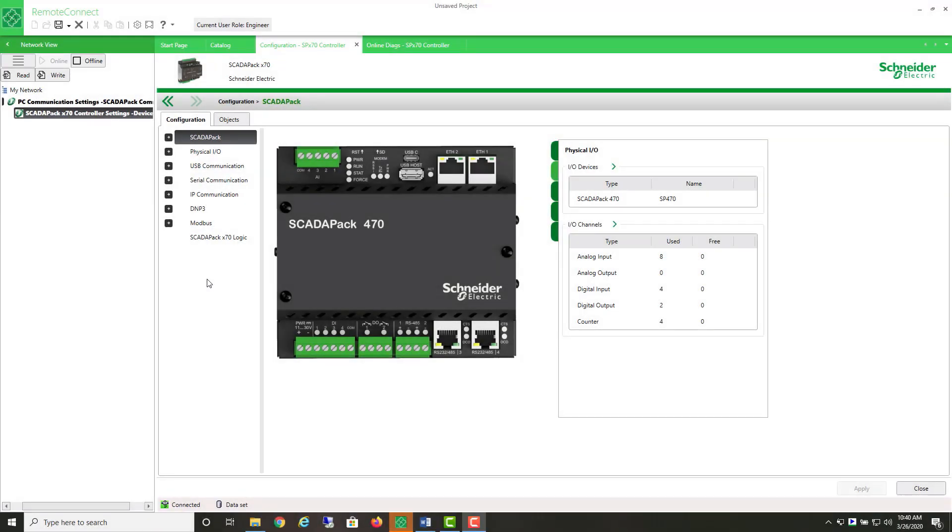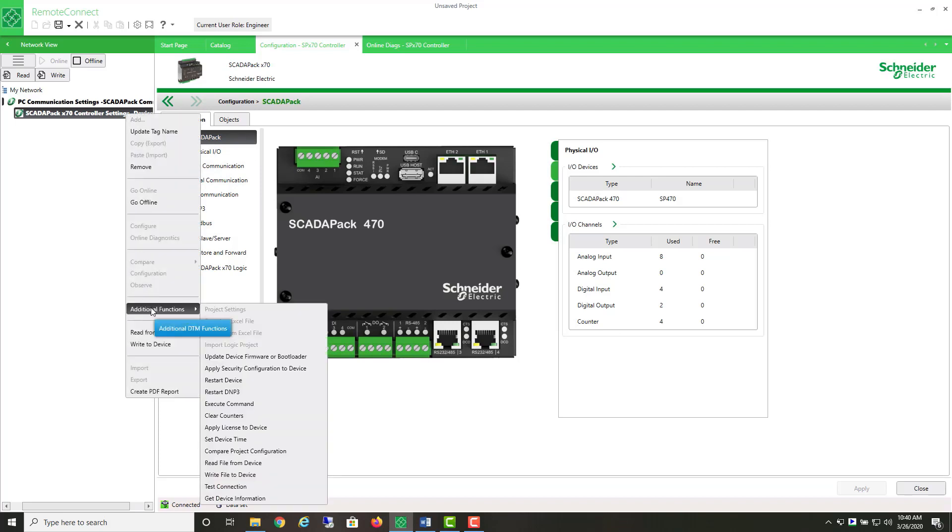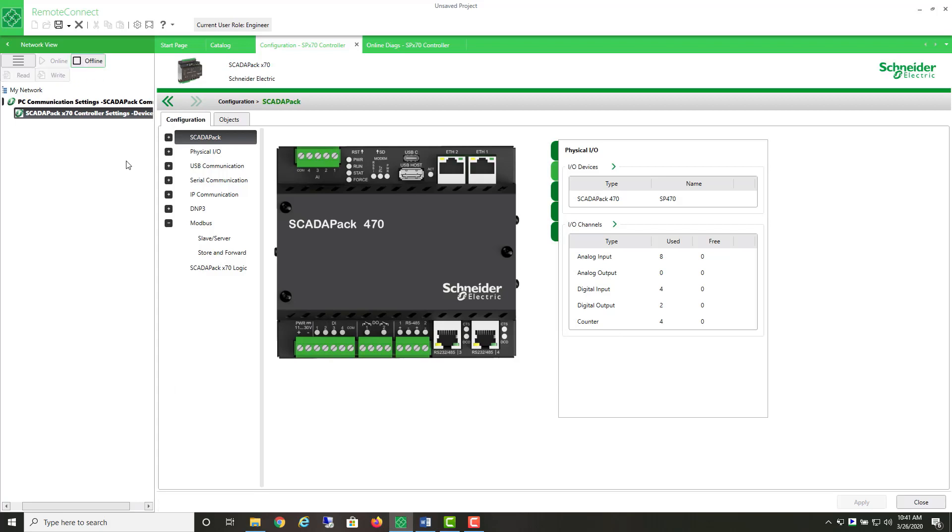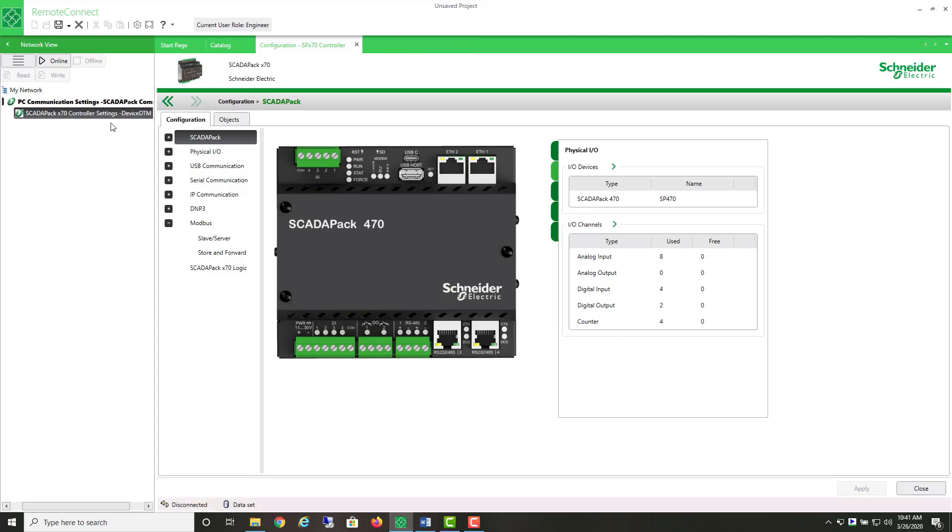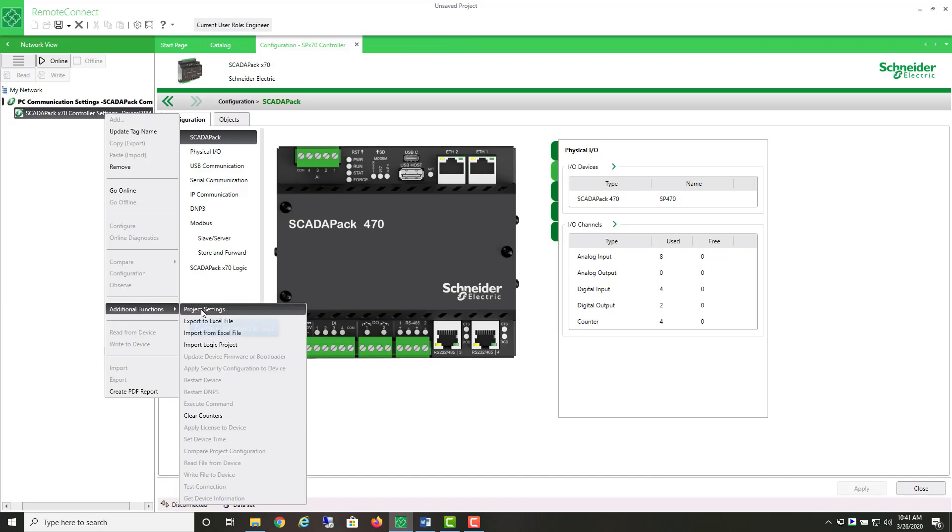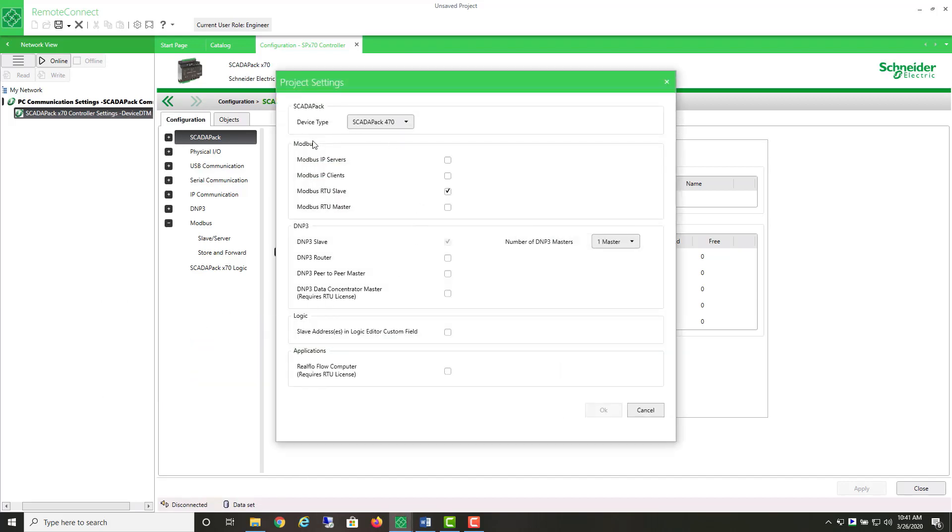If you're adding this to an existing project in Remote Connect, you'll find it under Modbus. It should be the Modbus master/client feature. But this feature has to be turned on when you initially created the project, or it can be added now. To add it now, we select this menu here. It's under additional functions, but it's the project settings, and we need to be offline to select it. So first we select offline. Under Modbus, the default is just to have Modbus RTU slave feature turned on. We want the Modbus RTU master.